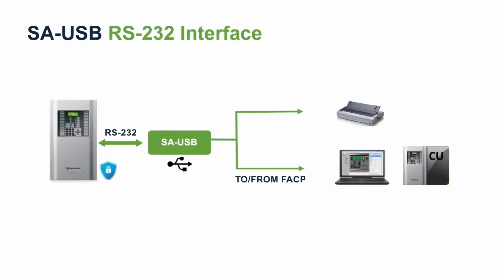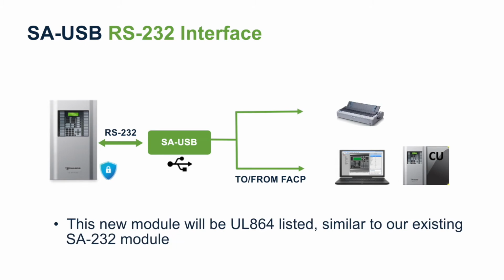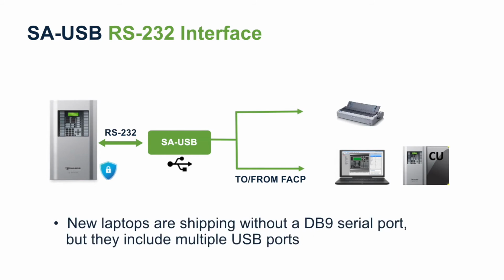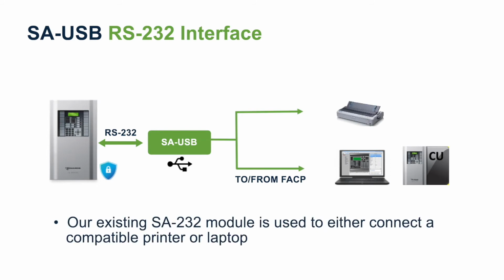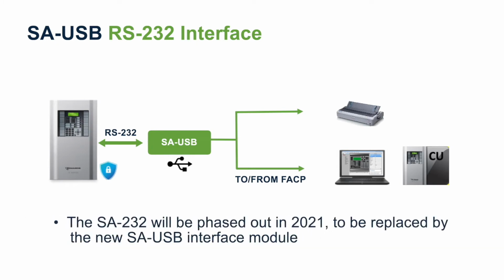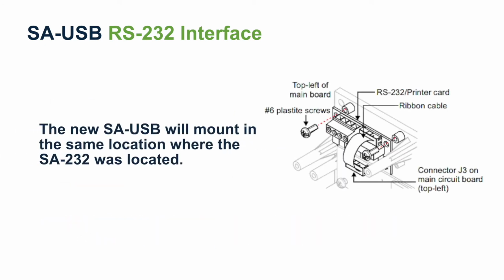Our next add is the new USB interface module. This new module will be UL listed as well, similar to our existing SA-232 module, because it will reside in the control panel and is used to configure and program the life safety system. And our upcoming SA-USB module is being introduced because new laptops today are shipping without DB9 serial ports, but provide multiple USB ports. Now our existing SA-232 module is used either to connect to a compatible printer, to the control panel, or the use of a technician's laptop running the configuration utility. The SA-232 will be phased out in 2021 to be replaced by our new SA-USB interface module. Now the new SA-USB will mount in the same location where the 232 was located.